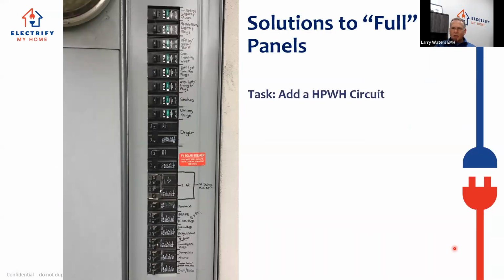So if we want to take this same electrical panel, I see now down here that they have a bedroom mini split. I never noticed that before. Let me see what the circuit size on this is. 20. So they have a bedroom mini split, they have an AC, they have a dryer, and they have the solar that was installed. This is obviously a 20 amp solar breaker, it looks like. Sorry, I need glasses for everything these days. 20 amp, that's part of getting in the trade before the first cordless drill. 20 amp solar, you guys could answer that question. That's probably under 4 kilowatts. But there's room in here.